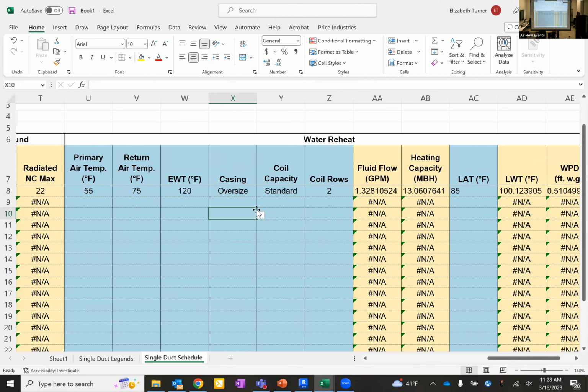And it's just better for us; we're happy to pick a lot of boxes. That's not a big deal. But then the engineer says, can you solve everything the same but change the leaving water temperature? It's like, no, you have to solve everything at once. And you have to pick your criteria. So it definitely is an engineering challenge to get a lot of heat out of a coil when the water temperature is so low without killing the system.